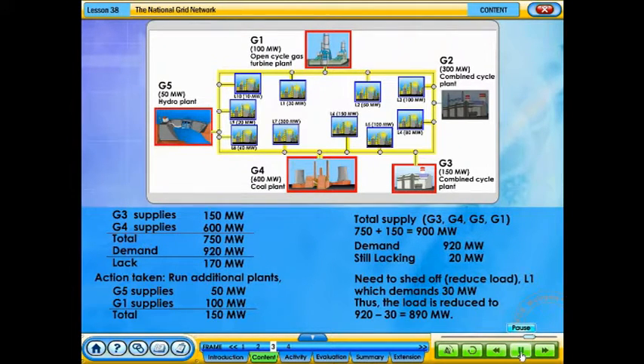Thus, there is a need to shed off or reduce load. The most appropriate load center to be shed off is L1, which demands 30 megawatts. This will reduce the load of the grid system to about 890 megawatts, which will be met by the generating capacity of 900 megawatts. Slightly more load is shed to cater for any fluctuation in the loads.